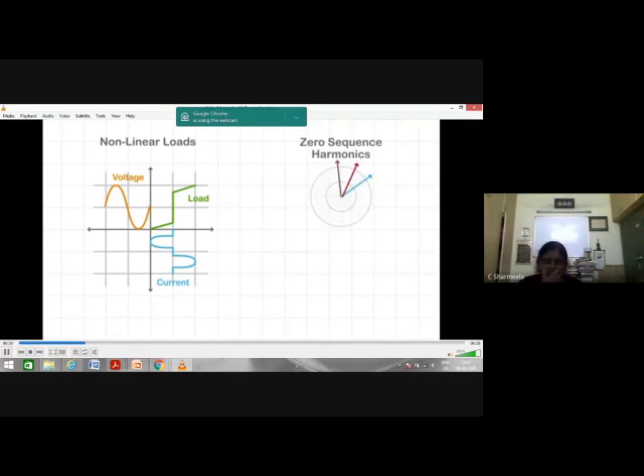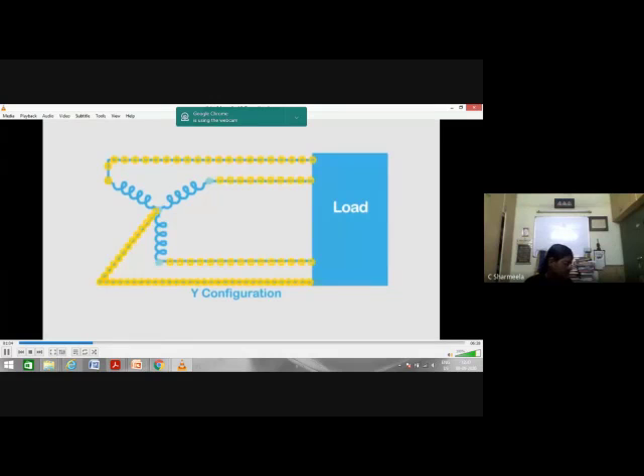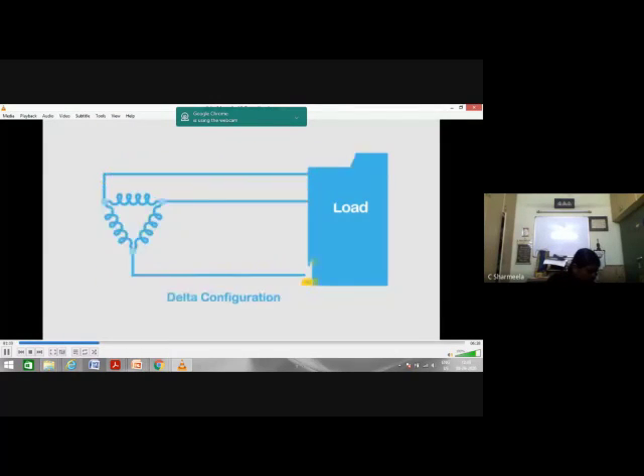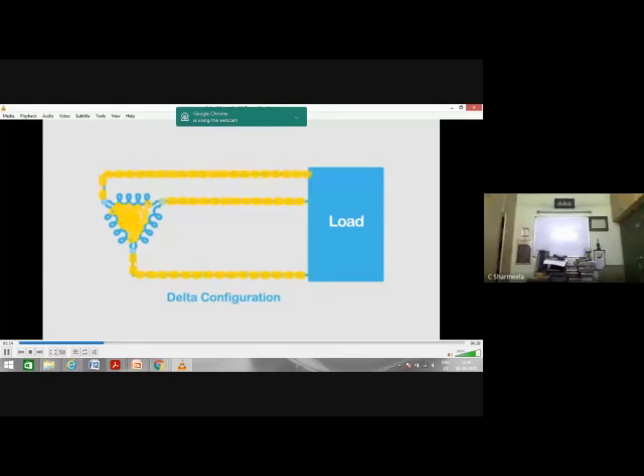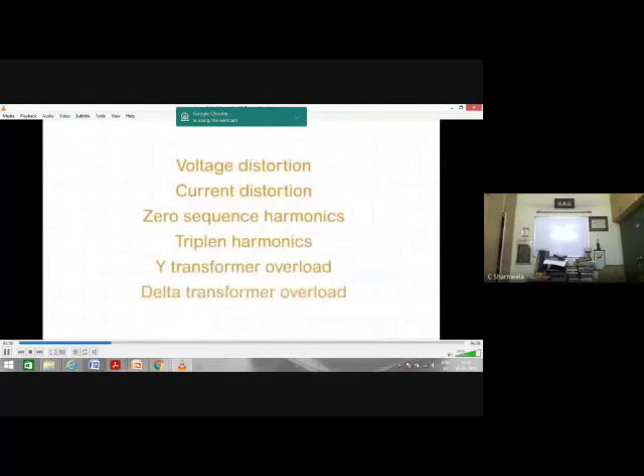Keep in mind that single-phase nonlinear loads like switch mode power supplies and lighting ballasts cause zero sequence harmonics. Third harmonic order, or triplen harmonics, in a Y configuration, add up in the neutral conductor of a Y system that can lead to neutral conductor overload. In a delta configuration, they get trapped in the delta of a delta system and can initiate magnetostriction within the transformer in question. All these effects can lead to premature equipment failure.